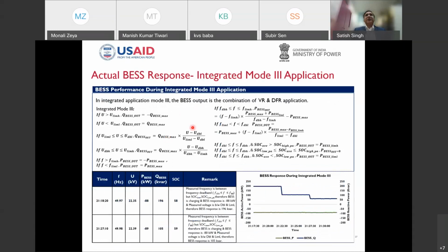The third piece, we wanted to integrate frequency application along with voltage support applications. So the same battery can be configured to provide different P and Q outputs. For example, if I say that from the same battery unit I'm going to use 30% for reactive power support and 70% for active power support, the kVA rating of the battery can be converted to P and Q, and accordingly we can get both responses at the same time. So the battery is doing the frequency regulation function, but it is also monitoring the voltage regulation.